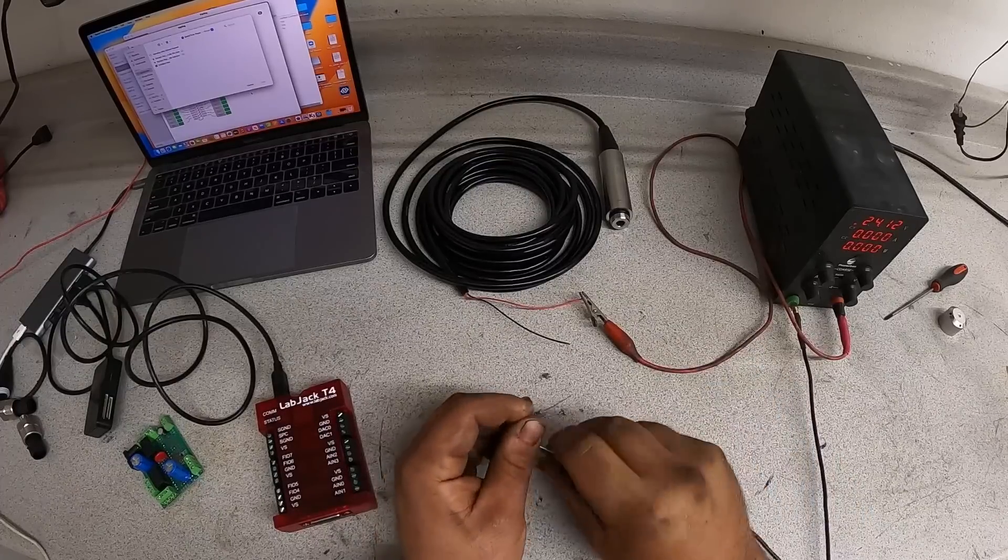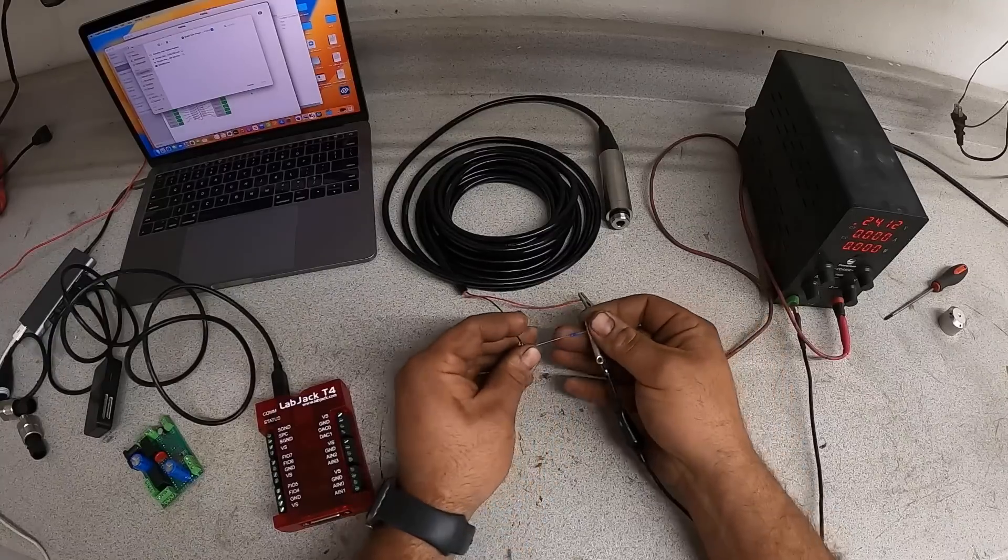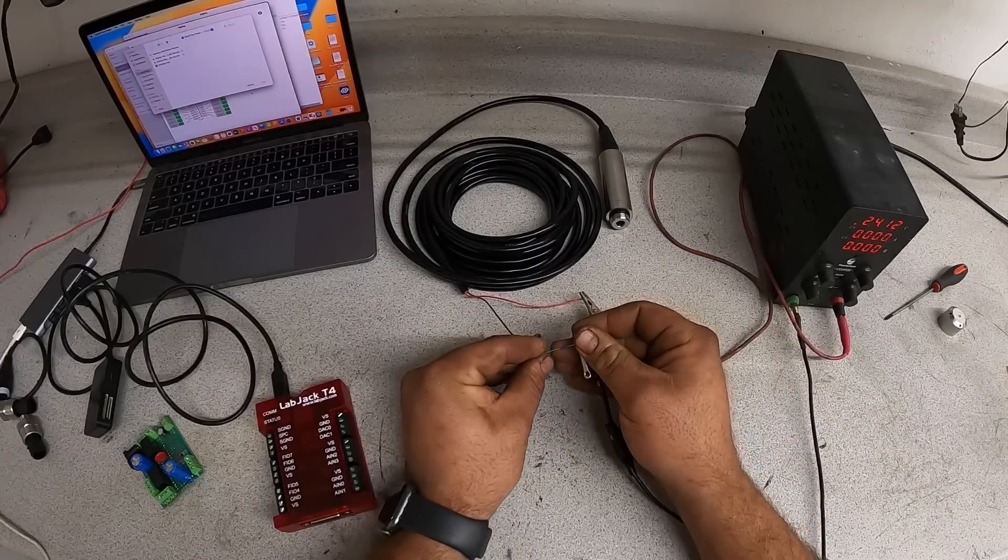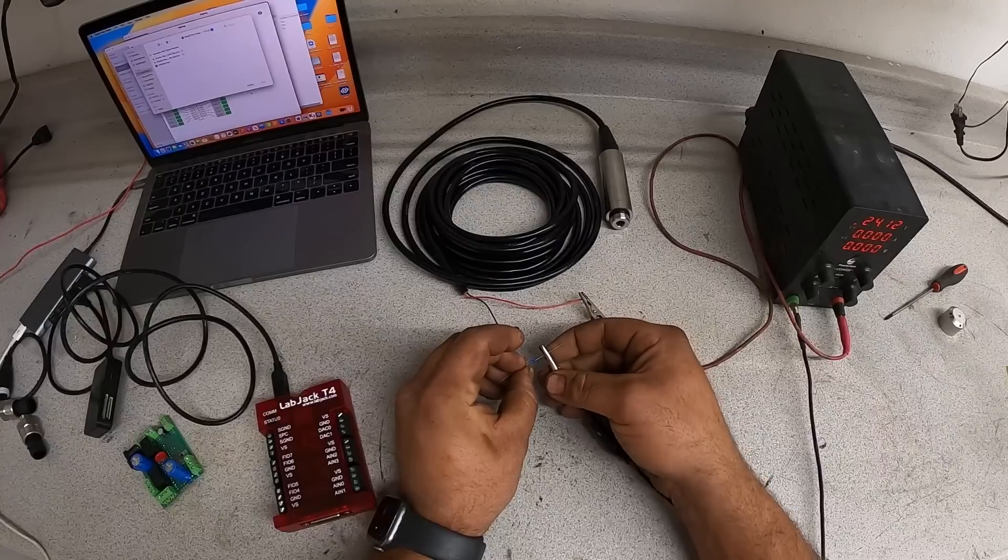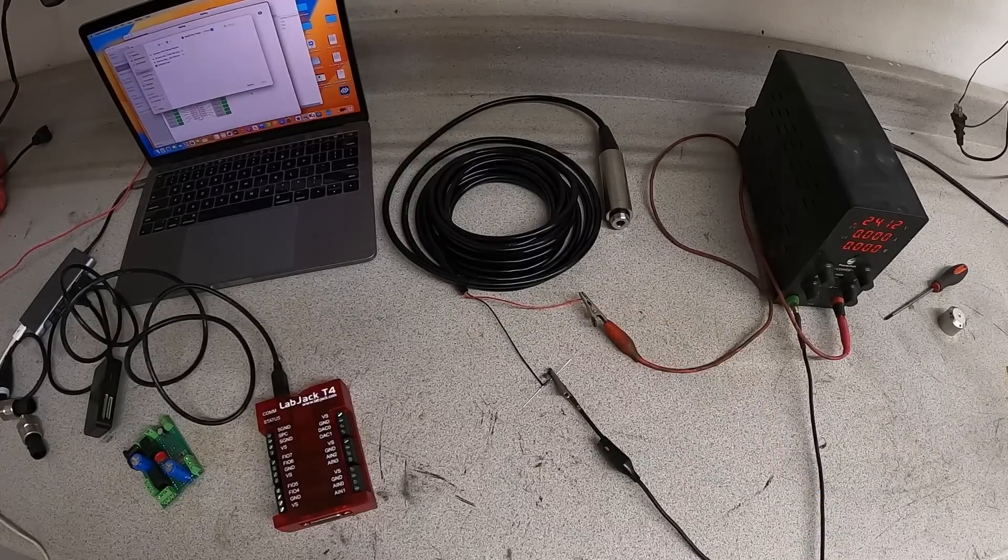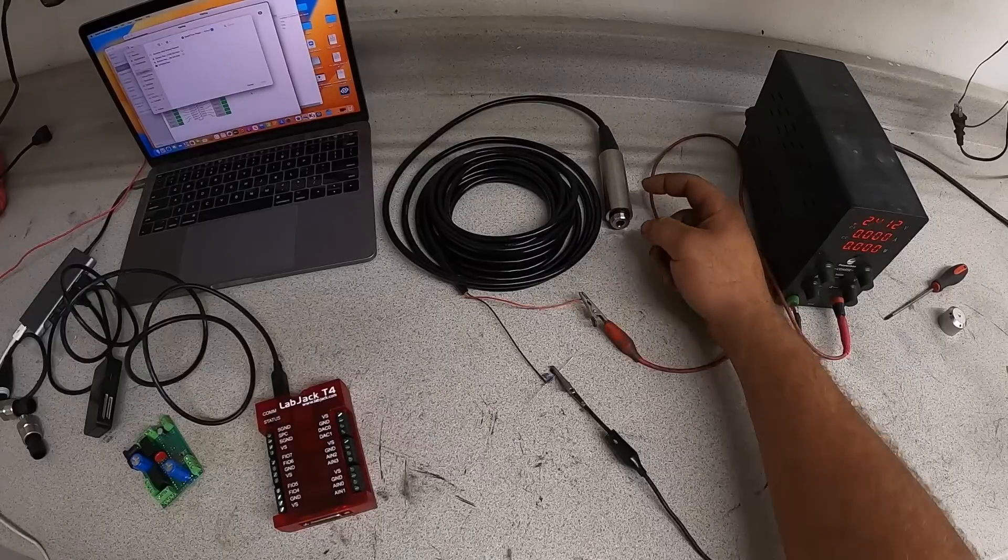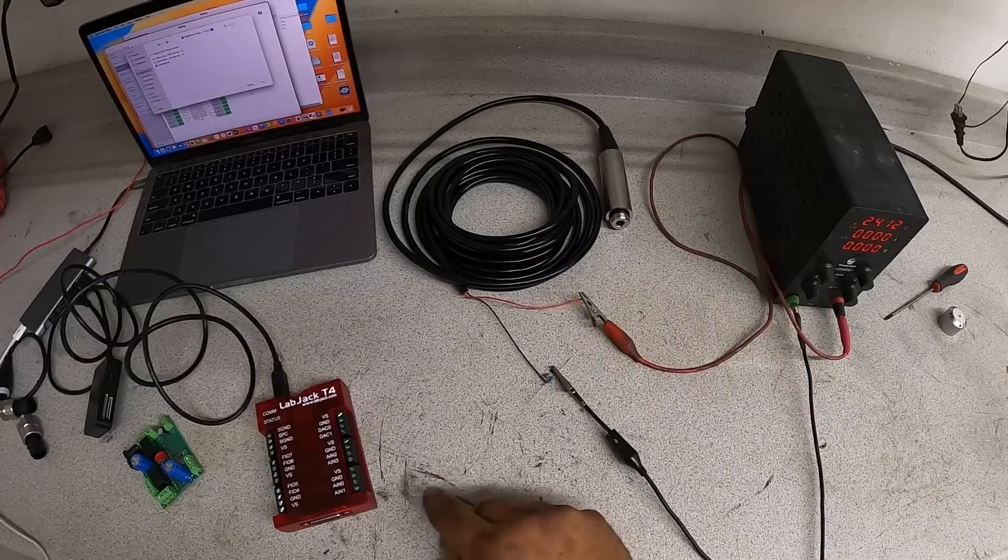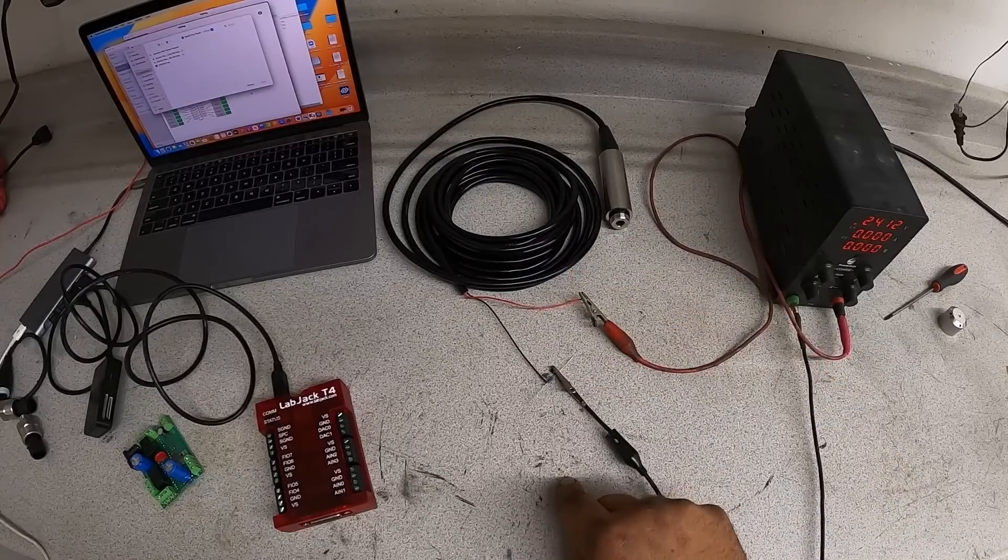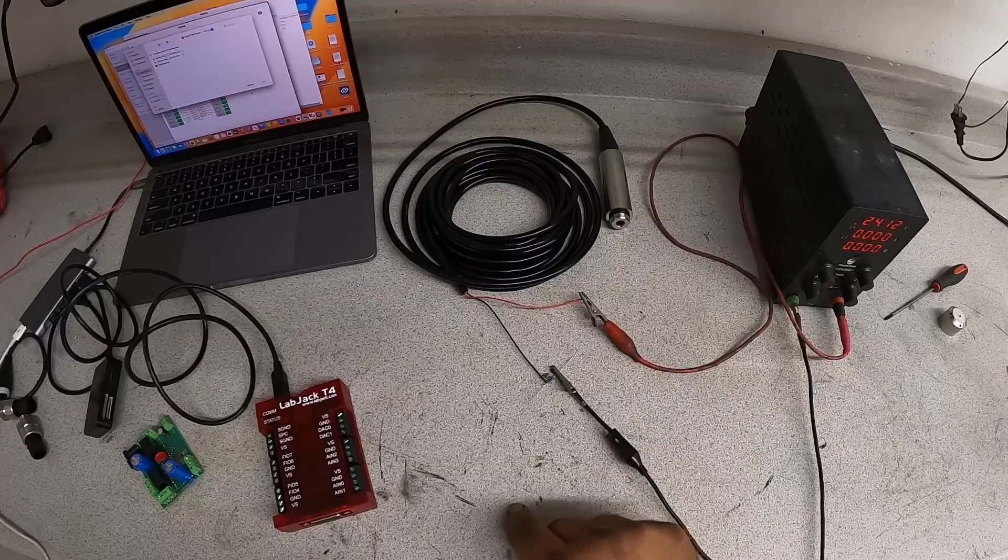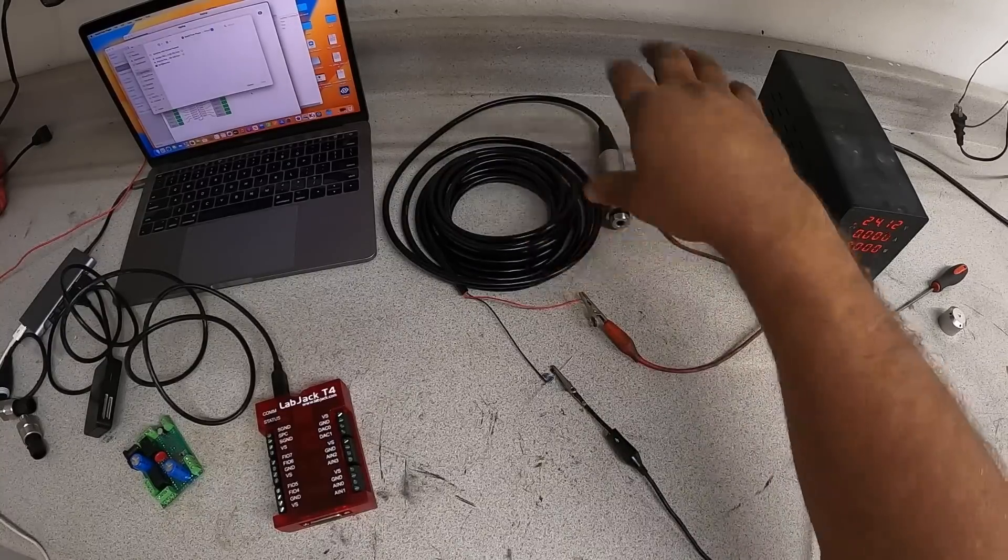Now to accomplish this, we're going to put in series here, in this circuit, we're going to put a resistor. This resistor has got a resistance of 100 ohms, which means for every amp of current you pull through it, it will have 100 volts across it. So we will have a maximum current here of 20 milliamps, or 0.02 amps, times 100 equals 2 volts.